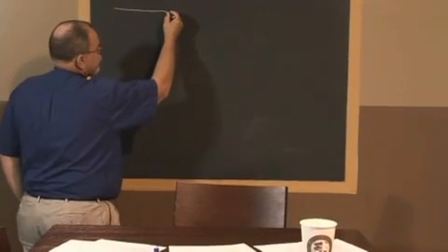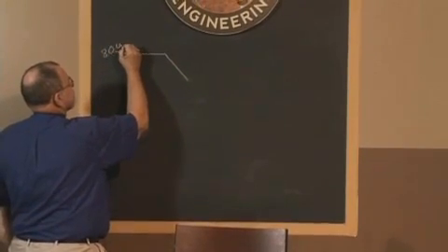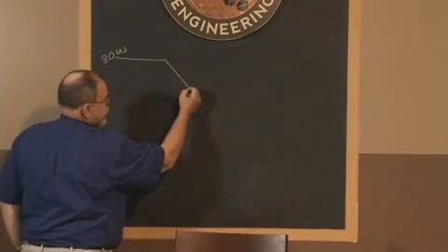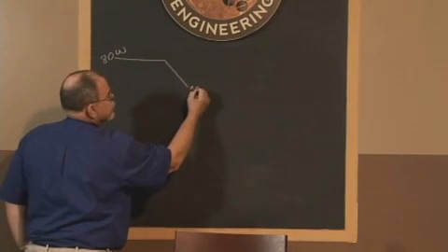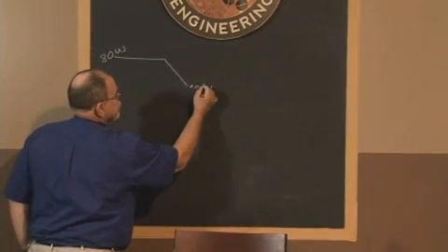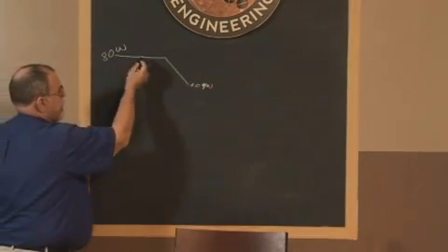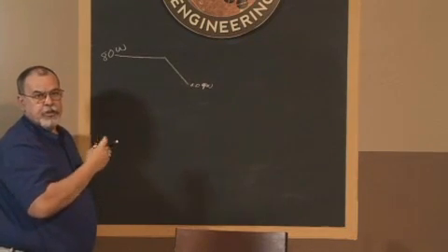So for discussion purposes, let us talk about the calibration. I'm going to kind of demonstrate this or draw it as we go through the discussion. There is a power limit that we described, and that is some forward power, and this happens to be 80 watts. And at the end, at 10 kilohertz, it's 0.09 watts. Now that's not real significant, other than 80 watts is a fairly high wattage, so we start warming things quite a bit.